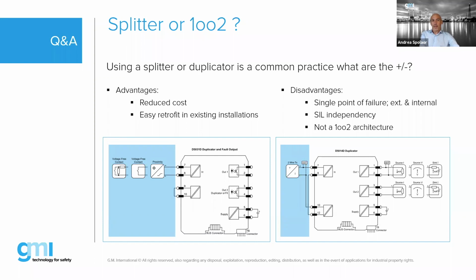In this case, yes, it introduces a single point of failure, and the field device is sometimes within the duplicator, so the units are not completely independent. We have two different channels in the unit that are repeating two outputs. But in this case, as we said, we have a single failure point, so we have the loss of SIL independency that is required, and the loop cannot be claimed anymore as 1 out of 2. So this is the main problem. You reduce the cost, of course, and it's a simple retrofit on your existing applications, but it's not safe anymore, it's not SIL anymore in this case.